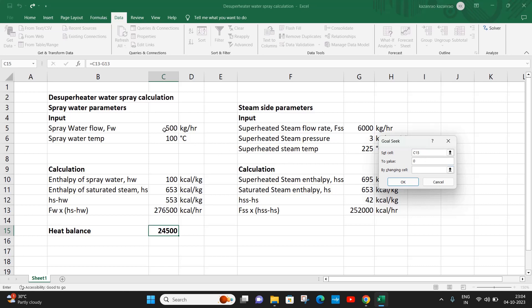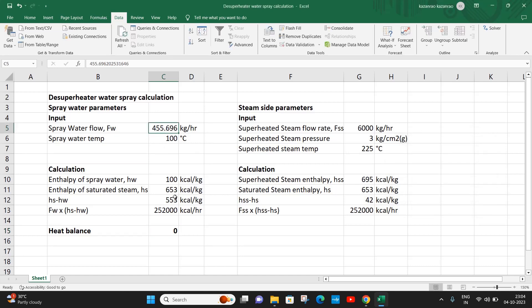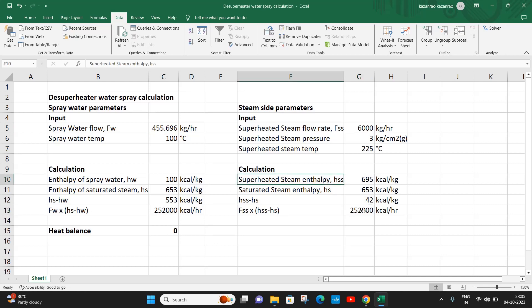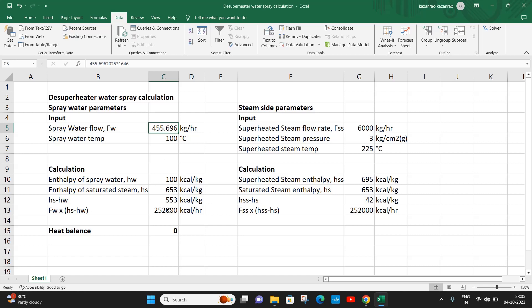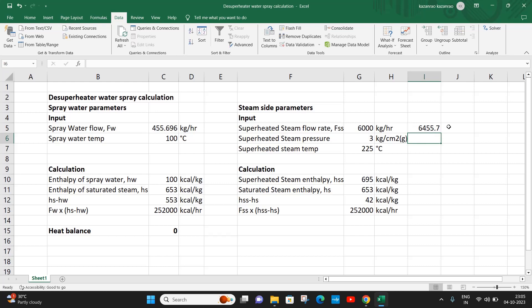Now 455.6 kg per hour, this is the spray water required to remove 252,000 kilocalorie from the superheated steam. This 252,000 gets added to 455 kg per hour of water, and that water also gets converted to saturated steam. So the final outlet steam after the desuperheat is 455.696 plus 6000, so this is the outlet in saturated condition.